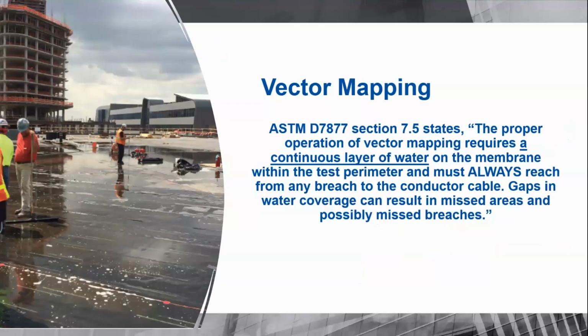So what you might hear is the addition of dish soap. Dish soap mixed with water helps to create a continuous film without flooding it. That's what you're seeing in this image. So again, the larger the area that gets isolated, the more water you need in a continuous path to carry that current. Gaps in that water coverage means breaches can be missed.